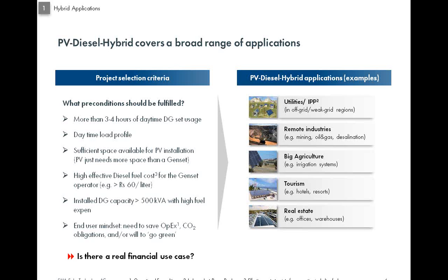Alright, so where can PV diesel hybrid be used? There are some preconditions. You cannot use them for all applications. Some preconditions are that the DG sets should be used at least 3 to 4 hours per day. The load profile should be significant during the daytime. You should have sufficient rooftop space for the module installation.